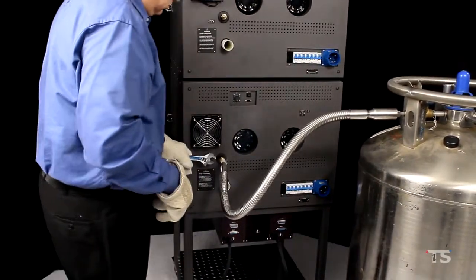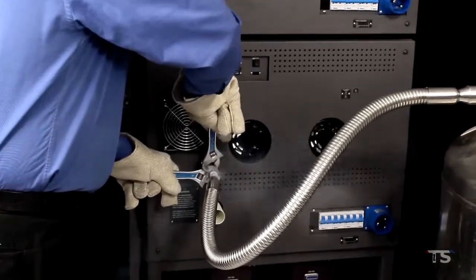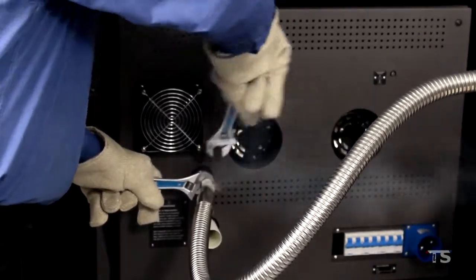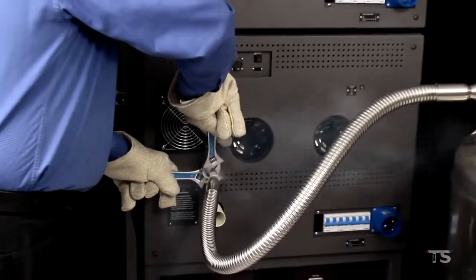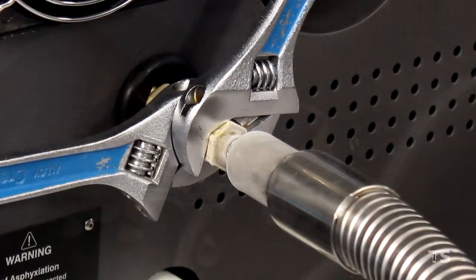Our attention should now be on the cryo inlet connections. We want to see the gaseous nitrogen vapor escaping from the hand-tightened connections. Once you are sure that gaseous nitrogen vapor is present, wait for the cryo inlet fittings to frost up. Once the fittings have frosted up, use your wrenches to fully tighten the connections.